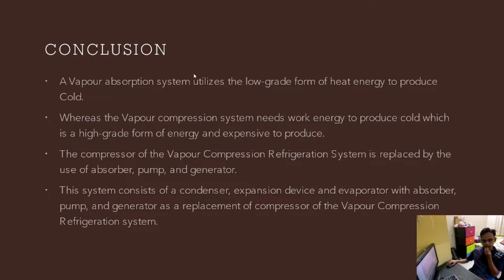A vapor absorption system utilizes a lower grade form of heat energy to produce cooling. So that means the absorption system has a low COP, whereas the vapor compression system needs work energy to produce cooling, which is a higher grade form of energy and expensive to produce. So the compression system has a higher COP.